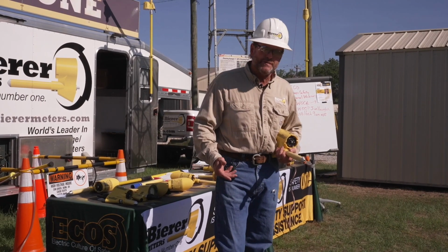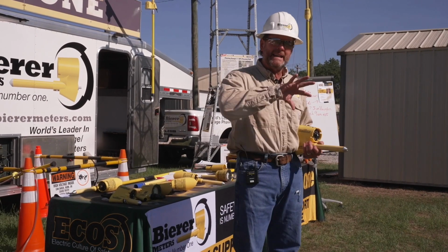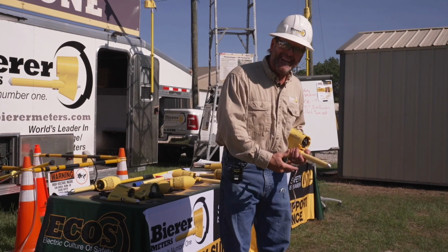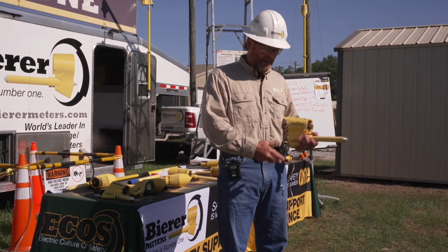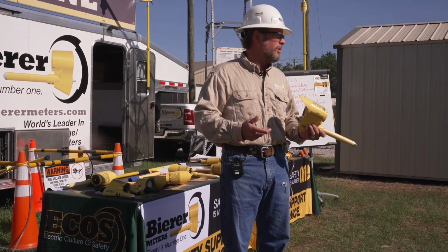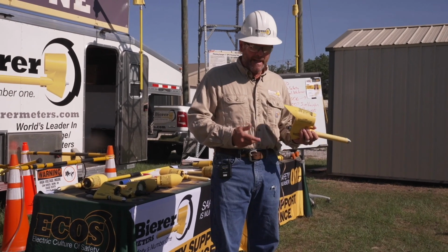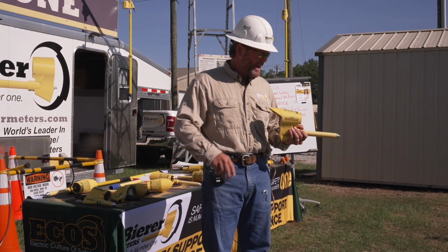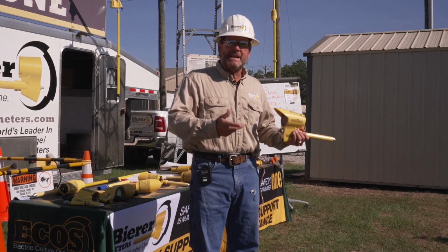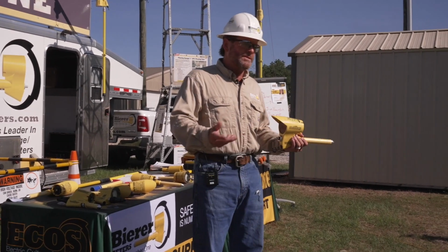So if that's how the tools function, they look at that current and the tool gives you a voltage indication or reading on the screen, whether it's analog, horn and light, or a digital meter. It's going to give you that voltage indication. So it's got to be energized. The tool must be energized in order to do so.